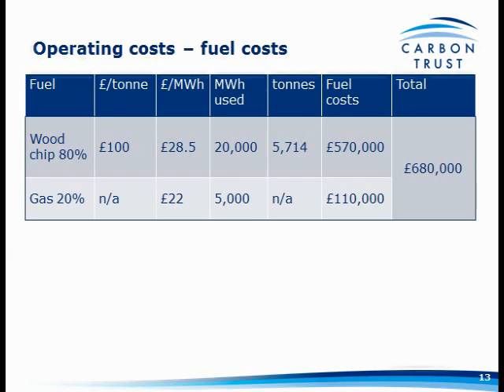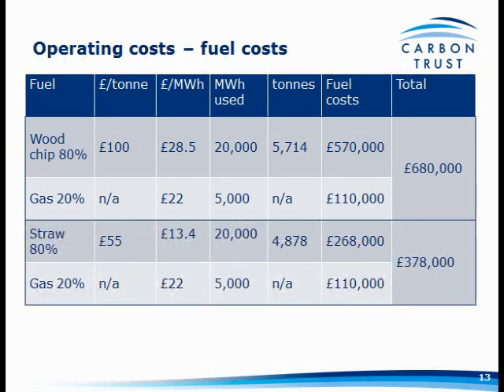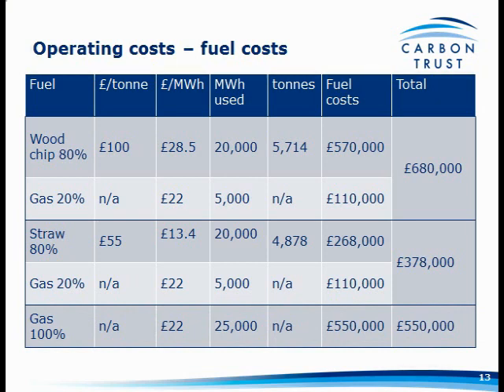In terms of fuel costs, based on Tim's nursery: if you're going to run 80% wood chip at £100 a tonne with the rest gas, it's going to cost you £680,000 to fuel that nursery for a year. If instead you use straw at £55 a tonne with the same 80/20 split, it's going to cost you £378,000. Compare that to 100% gas at 2.2p per kilowatt hour — roughly £22 per megawatt hour — which comes to £550,000.